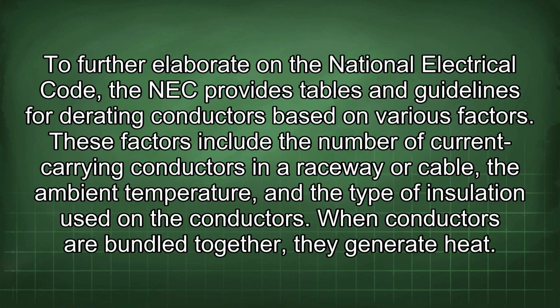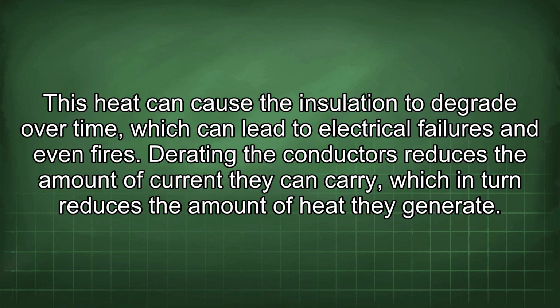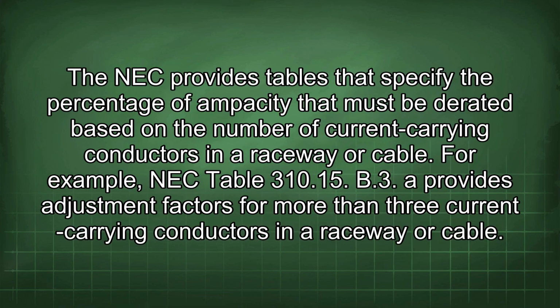To further elaborate on the National Electrical Code, the NEC provides tables and guidelines for derating conductors based on various factors. These factors include the number of current carrying conductors in a raceway or cable, the ambient temperature, and the type of insulation used on the conductors. When conductors are bundled together, they generate heat. This heat can cause the insulation to degrade over time, which can lead to electrical failures and even fires. Derating the conductors reduces the amount of current they can carry, which in turn reduces the amount of heat they generate. The NEC provides tables that specify the percentage of ampacity that must be derated based on the number of current carrying conductors in a raceway or cable.